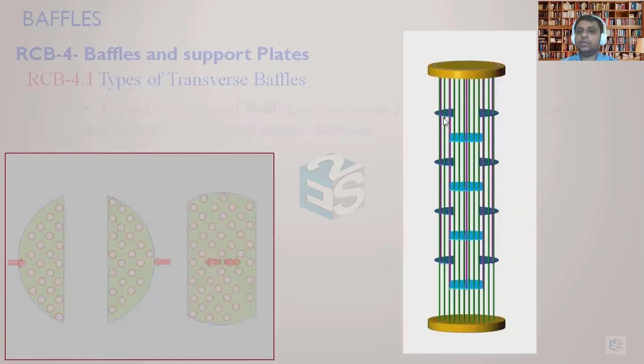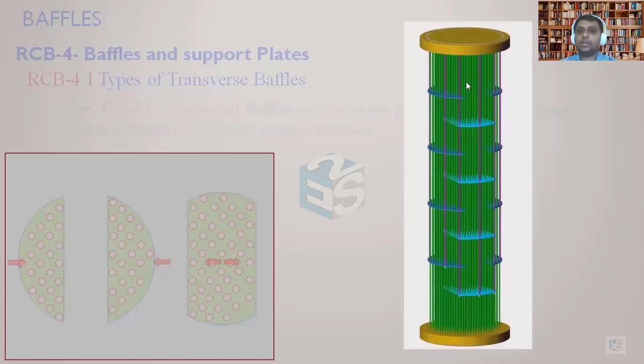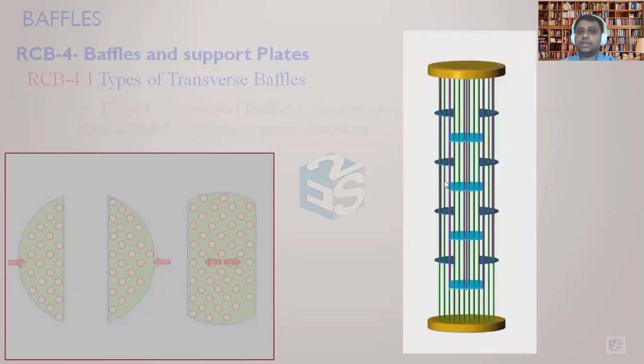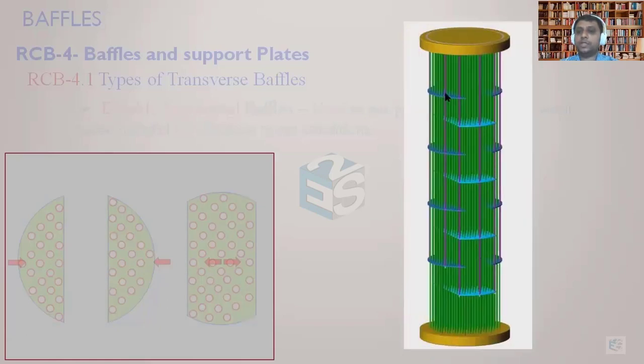So how will this look? Let's say the nozzles are mounted here and here. The flow will come from both sides, fall down from both nozzles, then move, fall again, and move again in a serpentine motion from both sides. This is the skeleton view where the tie-rod spaces are shown so you can clearly see how the baffles will be arranged. After adding the tubes, it will look like this. These are called double segmental baffles.